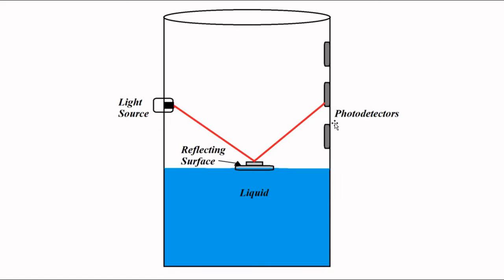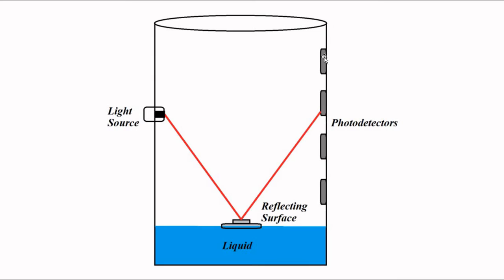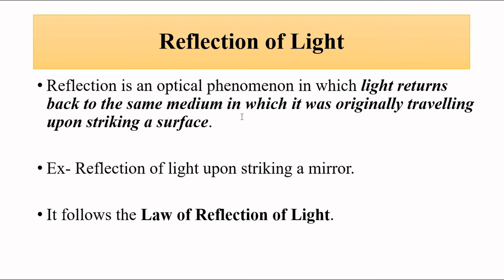The light undergoes reflection and falls on one of an array or series of photo detectors connected at the other end of the container. Depending on the liquid level, the position of the reflecting surface also changes. As a result, depending on the angle of incidence and the angle of reflection, the reflected light falls on one of the photo detectors in the series. By knowing which photo detector the light is reaching, we can determine the liquid level.